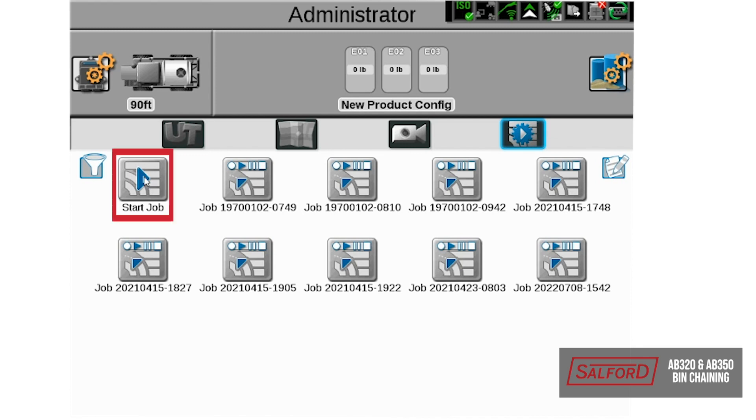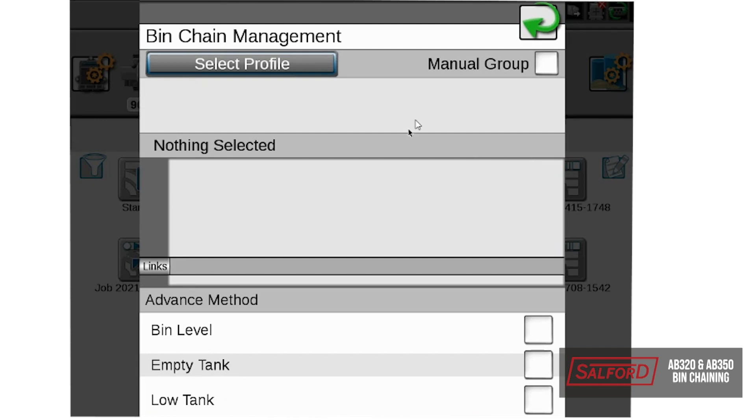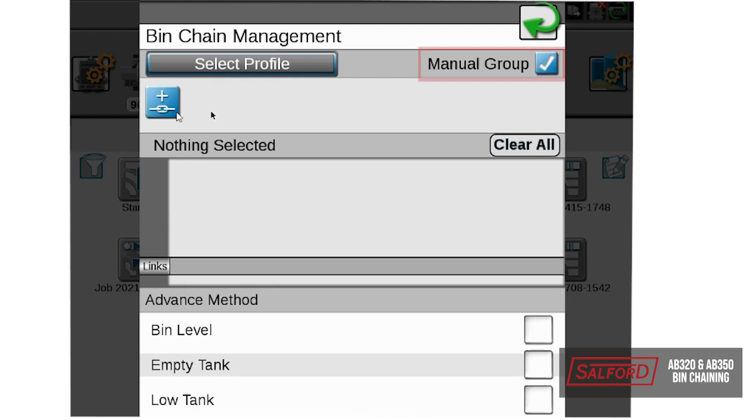First, we will select start job, and on this window, the first thing that we will do if we want the bins to be chained together is go to this tank assignment, select the chain link, and then to set up a profile, first we are going to select manual group, and then we are going to add a link.